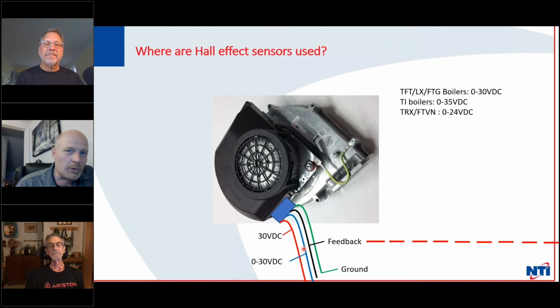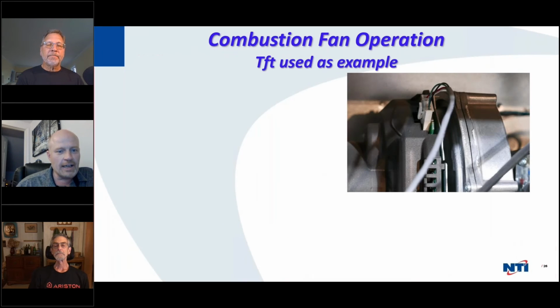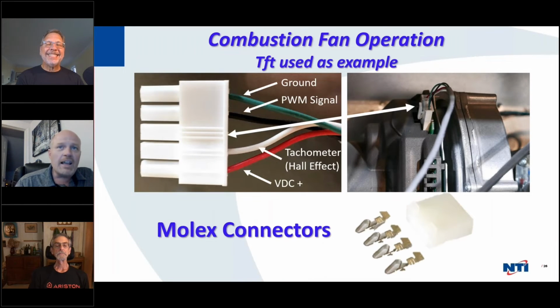And this kind of explains why when you disconnect this low voltage, the fan jumps to high speed. If you drop the difference between the two wires to 0 volts, as far as the fan is concerned, you've asked for 100% power. And that's why when removing the plug, the low voltage, it should jump to high speed, because as far as the blower is concerned, you've asked it to go full tilt. So we've got another slide on this, actually another couple. So this is a wire harness off a TFT, just as an example. So you can see the ground, the PWM is the variable voltage.